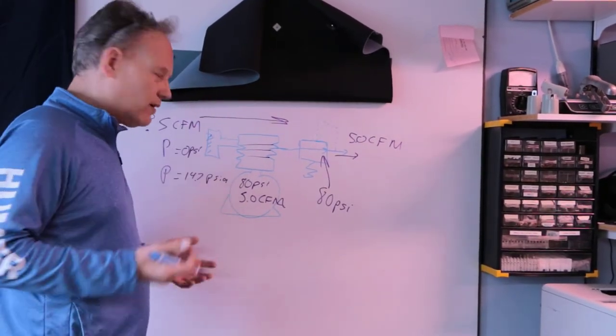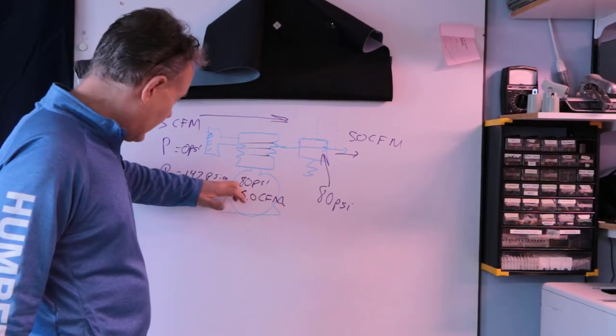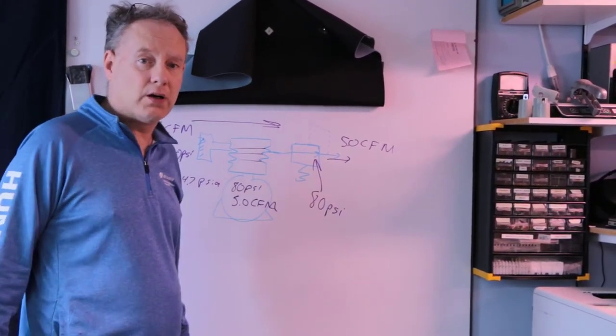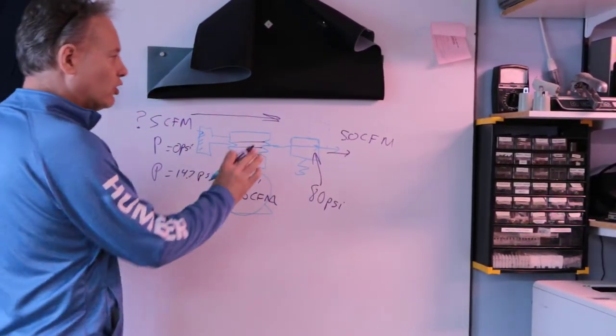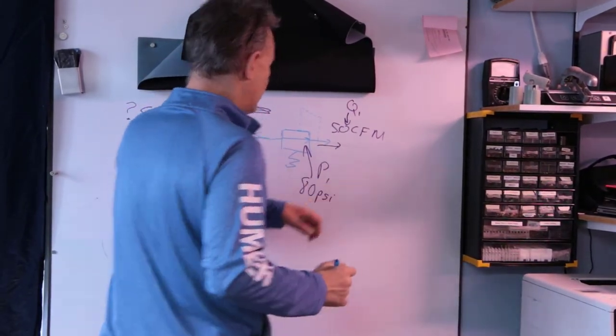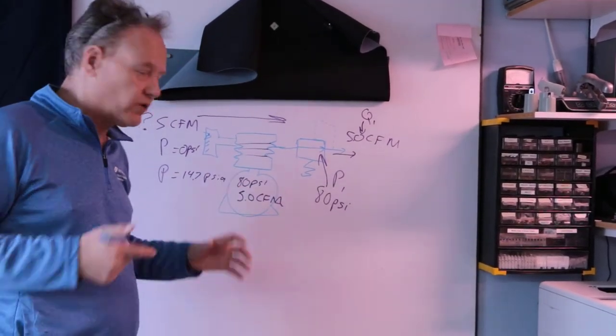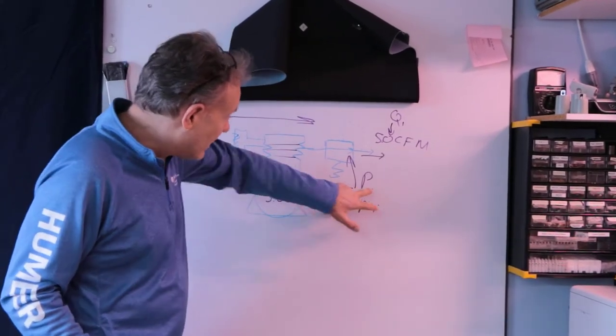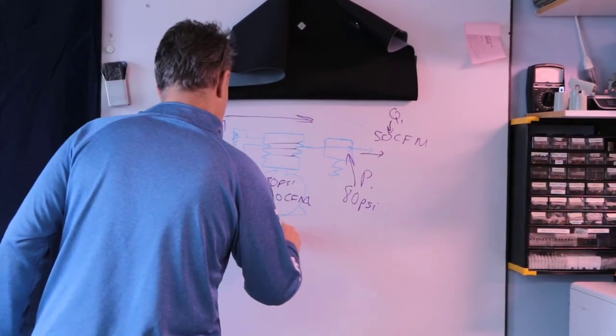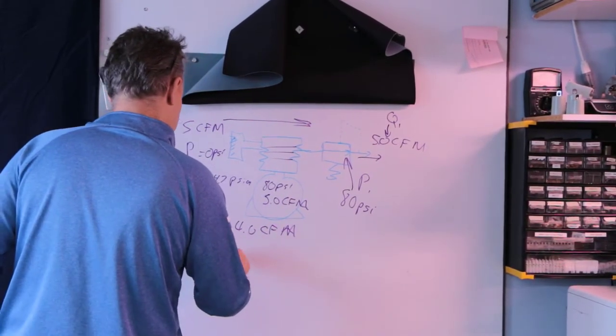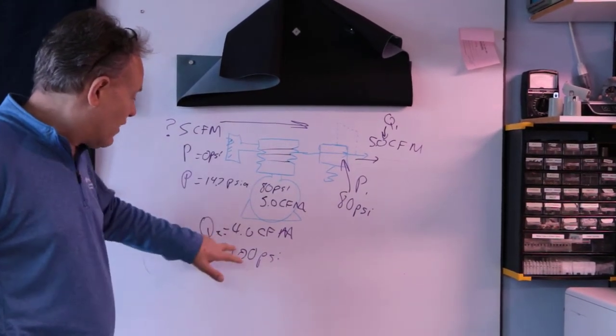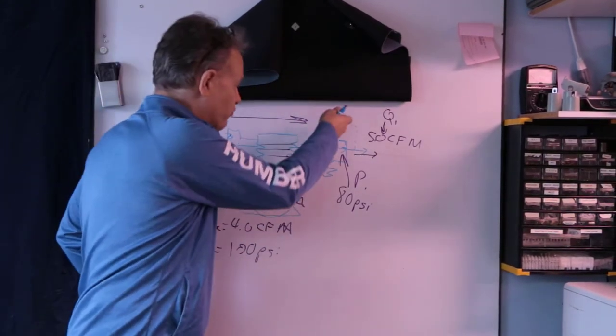My system needs to run on 100 PSI, and I only need four cubic feet per minute. I want to see if this compressor fits. So I'll call the rated condition Q1 and P1 — the before flow rate and pressure. If I set the compressor to 80 PSI it has a flow rate of 5 CFM. My Q2 is four cubic feet per minute and my P2 gauge pressure needs to be 100 PSI. The question is: will this give me four cubic feet per minute if I turn the regulator up to 100 PSI?